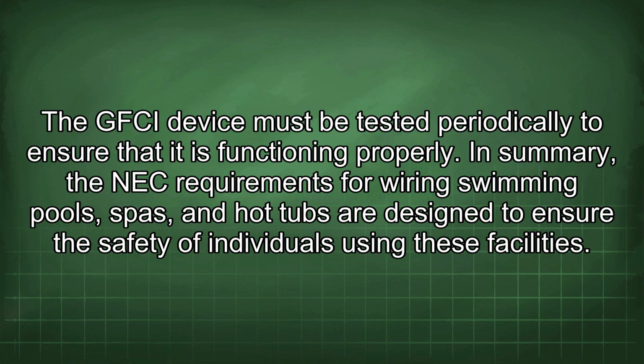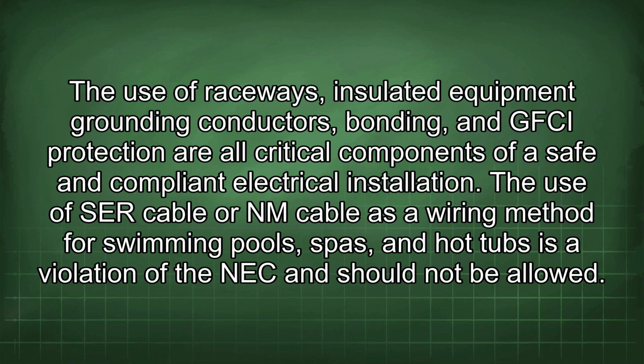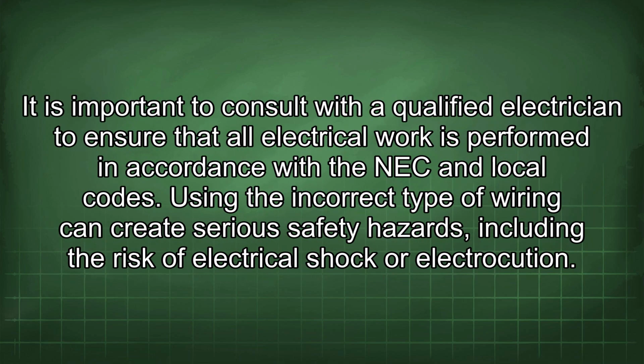In summary, the NEC requirements for wiring swimming pools, spas, and hot tubs are designed to ensure the safety of individuals using these facilities. The use of raceways, insulated equipment grounding conductors, bonding, and GFCI protection are all critical components of a safe and compliant electrical installation. The use of SER cable or NM cable as a wiring method for swimming pools, spas, and hot tubs is a violation of the NEC and should not be allowed. It is important to consult with a qualified electrician to ensure that all electrical work is performed in accordance with the NEC and local codes.